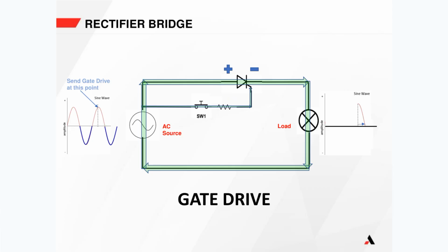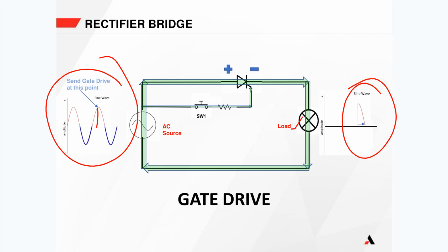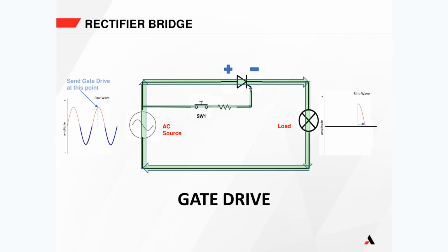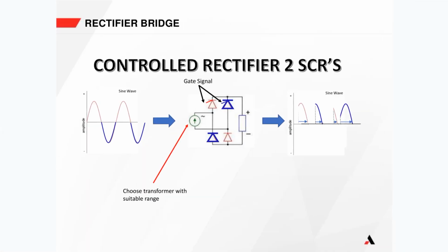So we have complete control over the output. We can choose when to switch that SCR on and allow some of the sine wave through to create DC. In this waveform, we only switched it on for this one cycle, so that's the only cycle that gets through to our load. If we replace two of the diodes in the previous bridge with SCRs, then for every single half wave we can change when the SCR turns on, and therefore regulate how much voltage is coming out of the charger.